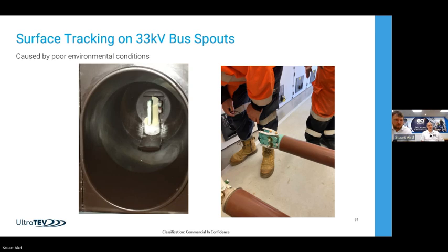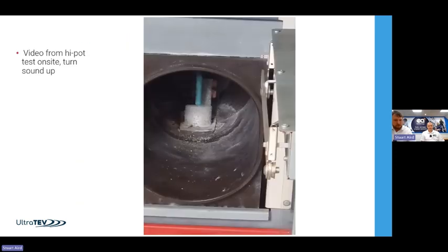So this is showing the actual corrosion of the connections here, and this is through environmental conditions, what's caused that tracking on the spouts. The next page is this taken offline and energized from a low energy source and recorded from a safe distance, and you'll see here just what the arcing looks like. You should see marking and sparking going on there.